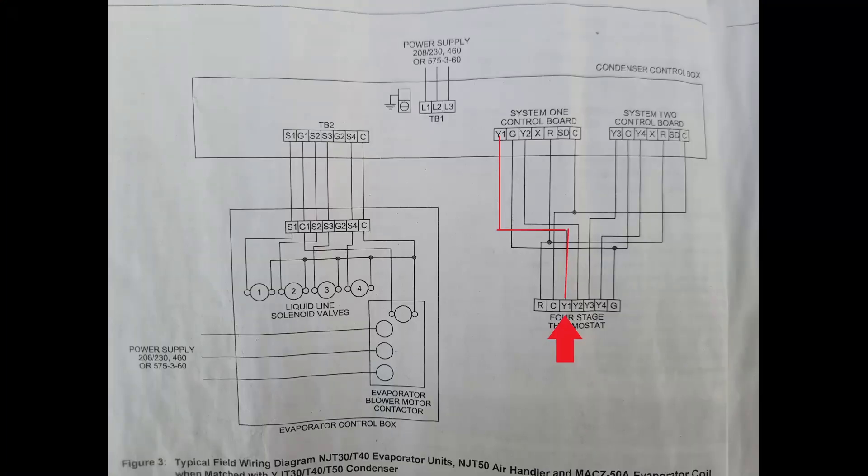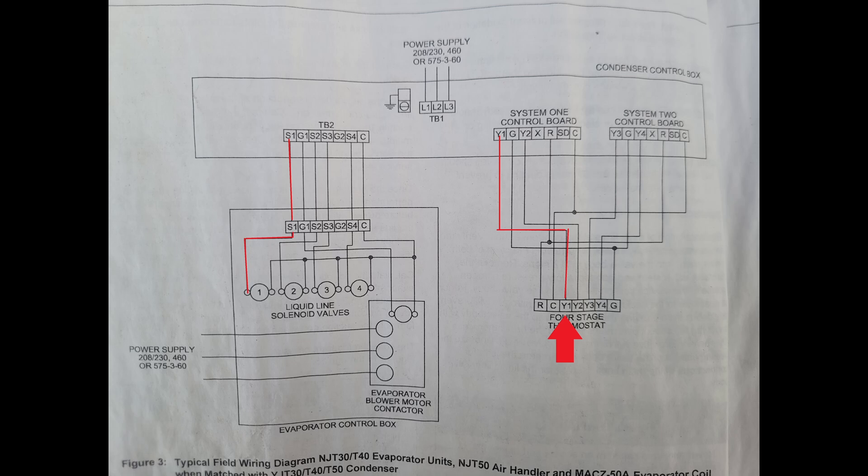Okay, so here it is on the diagram. You can see Y1 coming up from the controller. And then S1 engages, comes back down to the liquid-line solenoid on its own timing based on the pump-out relay. And then that all works great.